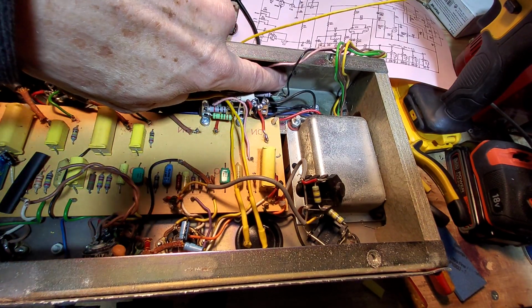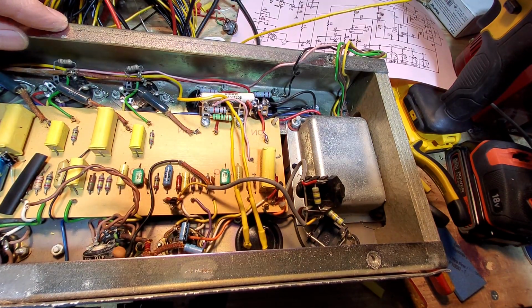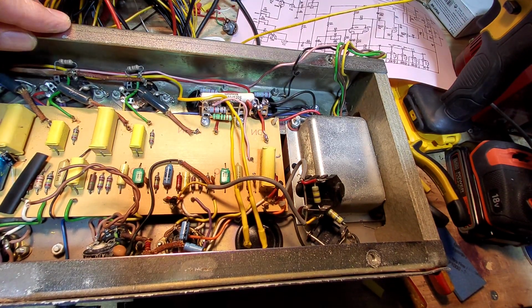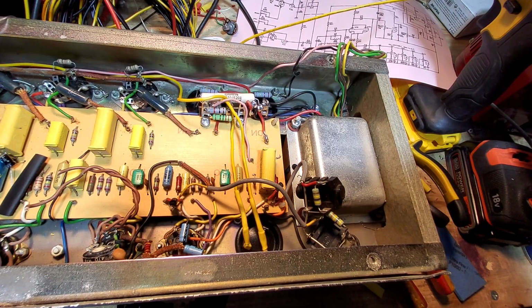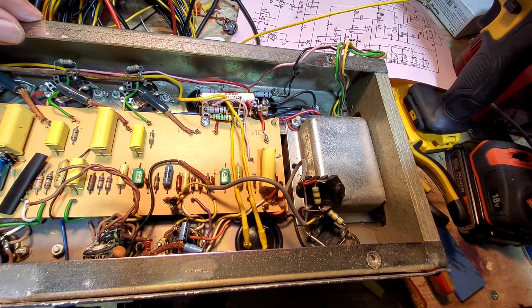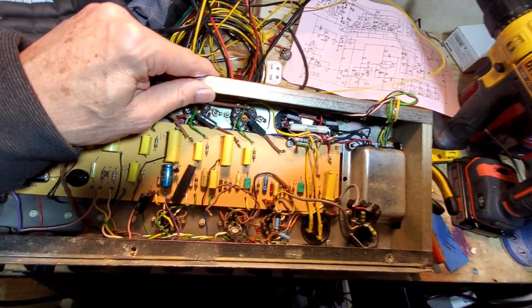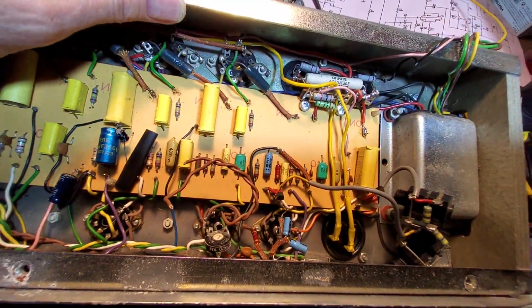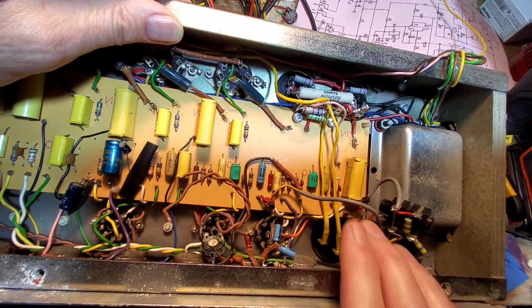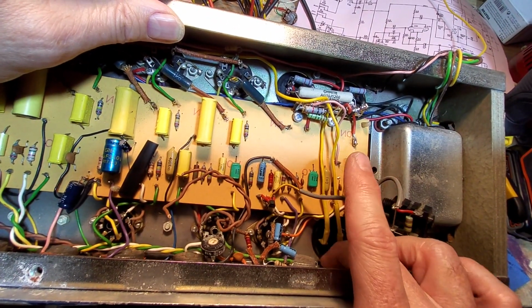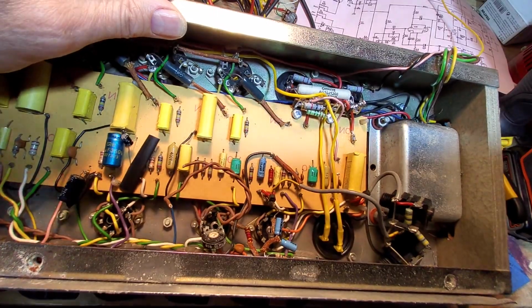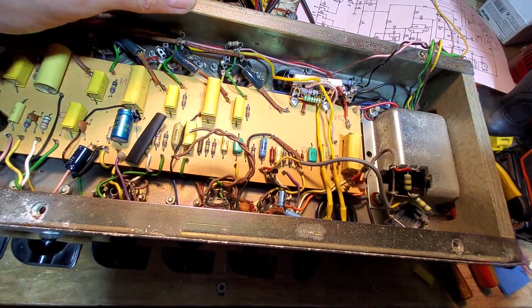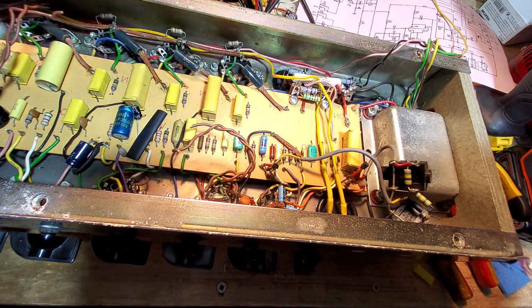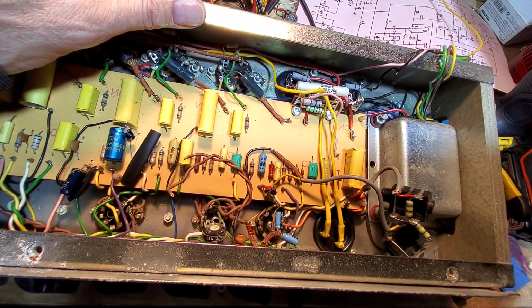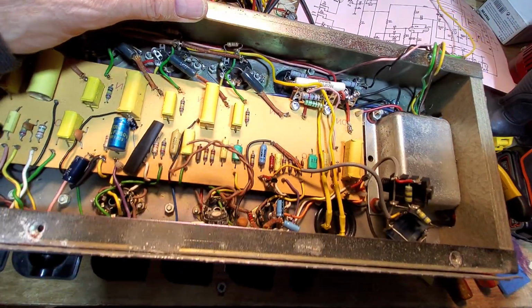Such as that one there, where you can see just a very flimsy ground. That's only on the ground for the speakers, so that's not a huge deal, but when we're dealing with nearly 500 volts we need a decent ground. Also, if we look at our capacitor down there, you can see we've insulated those, and we've got that rubber grommet blanking thing there, and that's made it safe. So now if anybody's in here tinkering to tighten up the jack socket, well, because you never know, people do daft things, don't they? I do daft things all the time.